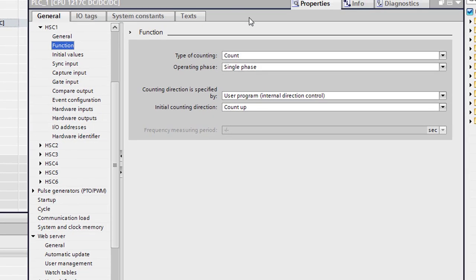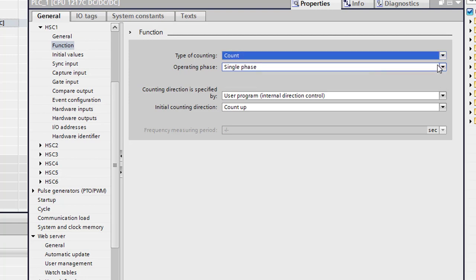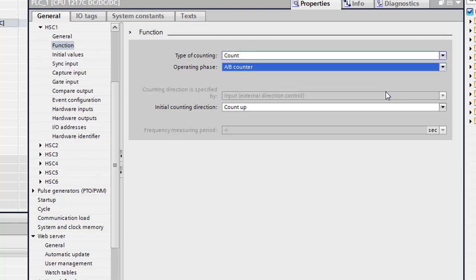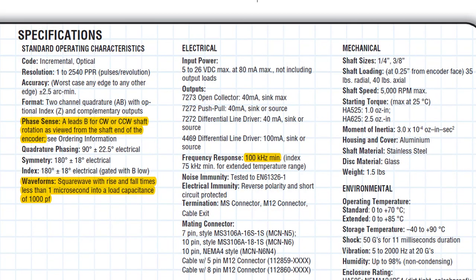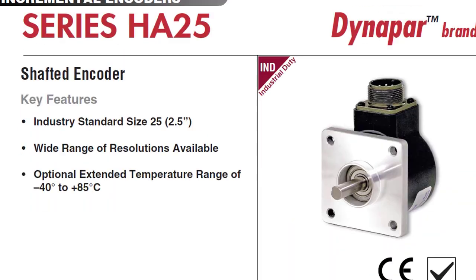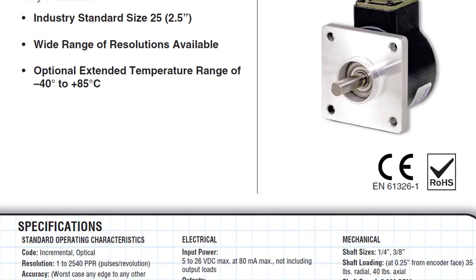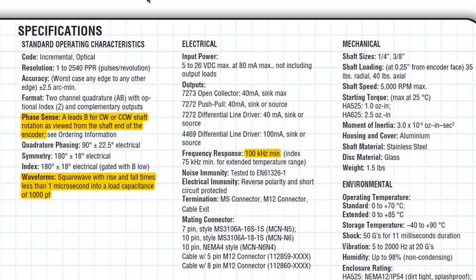And we're going to select a function for it here. Let's just give this whole window focus. So we're going to use the type of counting. We're going to use count. There are other options in here. And I know I have an AB counter, and I went in and I pulled up the information on this one. It is a Dynapar. It's an HA625 is the one that we have. The phase sense is A leads B for clockwise or counterclockwise shaft rotation as viewed from the shaft end.